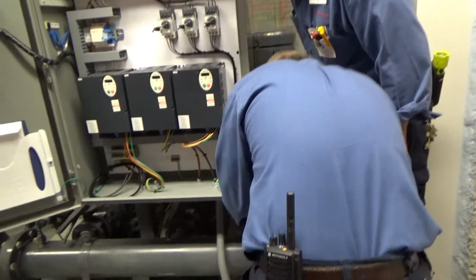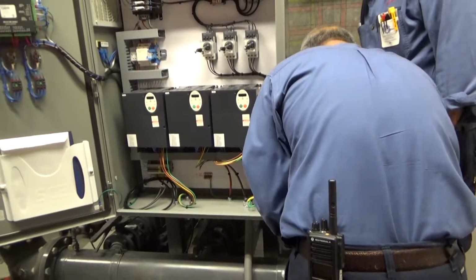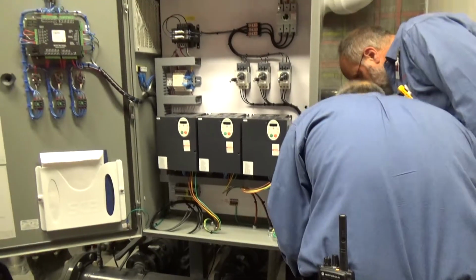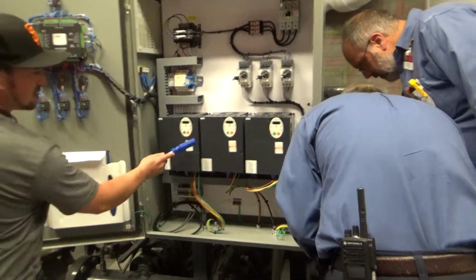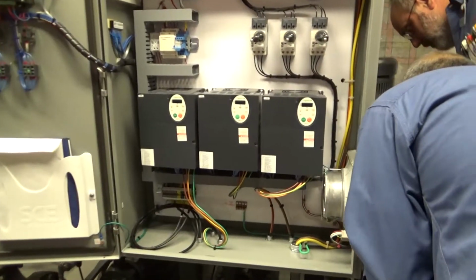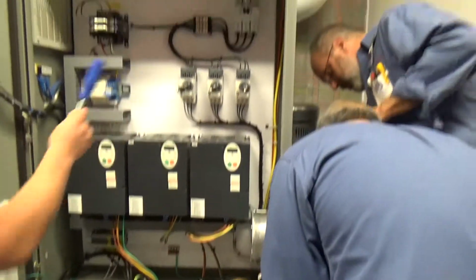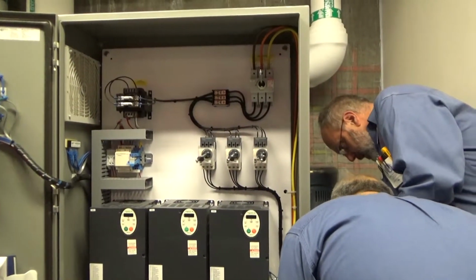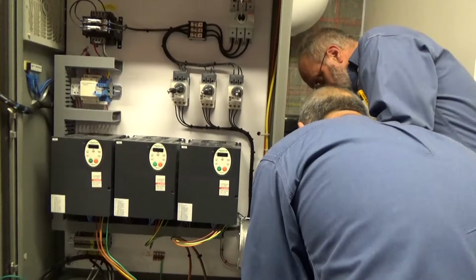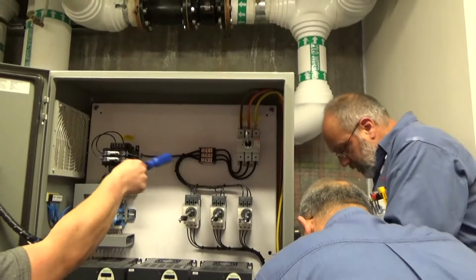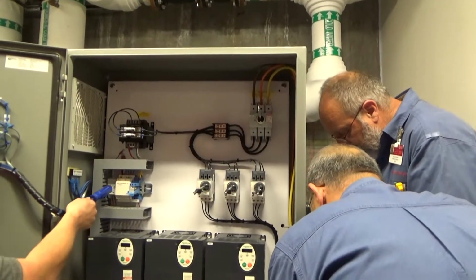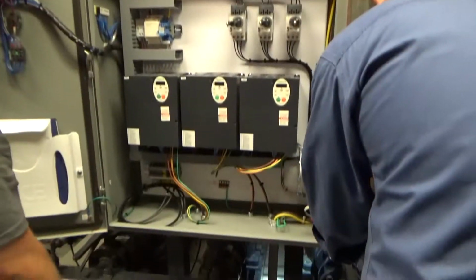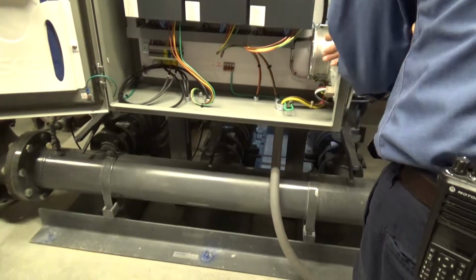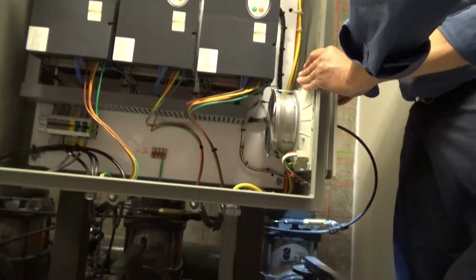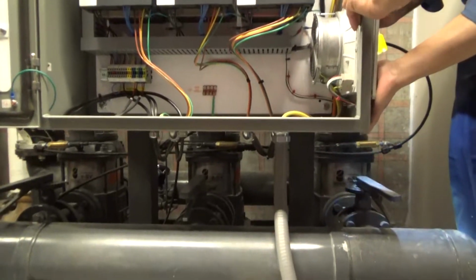Dirty filter, dirty air coming in. Like all this dust in there. So while I have it open, you have your VFDs right here. They're made by Schneider Electric. These are your overloads that are in accordance with the amperage on those motors. This is your main disconnect. You got branch off, you got transformers, temperature setting for your fan, a little terminal block for your transducers and temperature sensors and all that good old stuff.